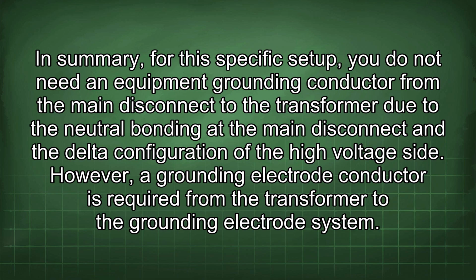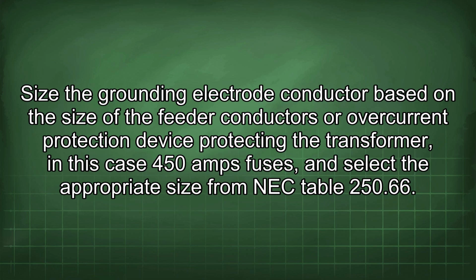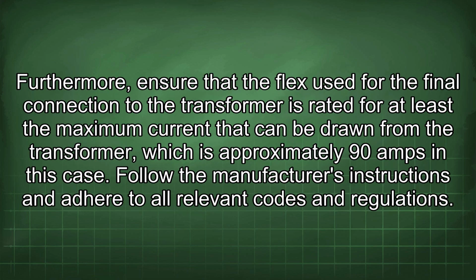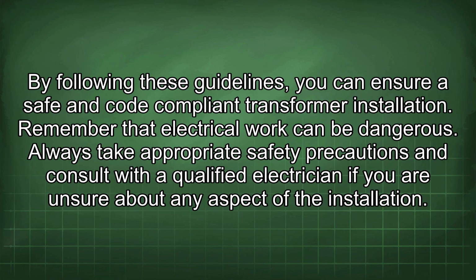However, a grounding electrode conductor is required from the transformer to the grounding electrode system. Size the grounding electrode conductor based on the size of the feeder conductors or overcurrent protection device protecting the transformer, in this case 450 amps fuses, and select the appropriate size from NEC Table 250.66. Furthermore, ensure that the flex used for the final connection to the transformer is rated for at least the maximum current that can be drawn from the transformer, which is approximately 90 amps in this case. Follow the manufacturer's instructions and adhere to all relevant codes and regulations. By following these guidelines, you can ensure a safe and code-compliant transformer installation.